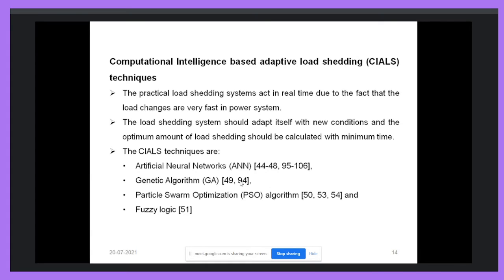You saw that in the relay based load shedding technique, the relay system does not bother about the real time parameters. Once you have set the relay setting, once you define the frequency setting, it will operate according to that. It does not see what the generation is at present or what the connected load is at present. It will just monitor the frequency of the system and issue the tripping signal if the frequency goes below the set value. But in the computational intelligence based adaptive technique, it will continuously monitor the actual generation of the system at present, the connected load, the spinning reserve, and the other conditions of the system. Accordingly, it will act on the operating condition of the system. So this is the benefit of computational intelligence based techniques.